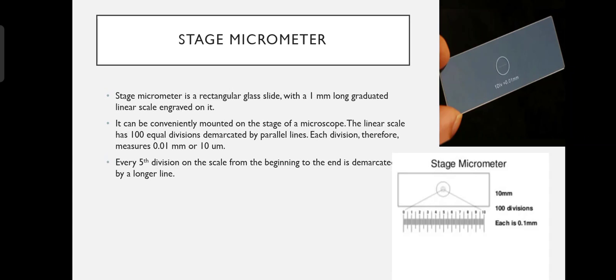It can be conveniently mounted on the stage of the microscope. The linear scale has 100 equal divisions demarked by parallel lines. Each division therefore measures 0.01 mm. Every fifth division on the scale from the beginning to the end is demarked by longer lines.